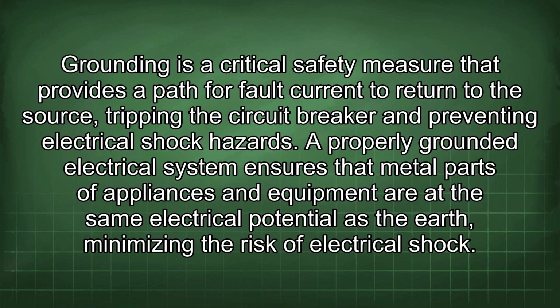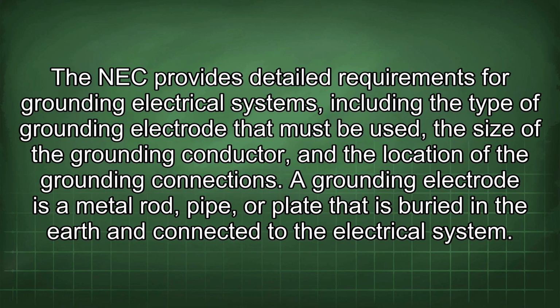Grounding is a critical safety measure that provides a path for fault current to return to the source, tripping the circuit breaker and preventing electrical shock hazards. A properly grounded electrical system ensures that metal parts of appliances and equipment are at the same electrical potential as the earth, minimizing the risk of electrical shock. The NEC provides detailed requirements for grounding electrical systems, including the type of grounding electrode that must be used, the size of the grounding conductor, and the location of the grounding connections.